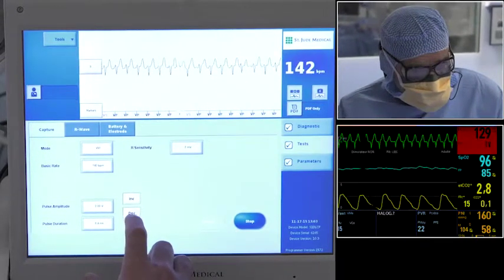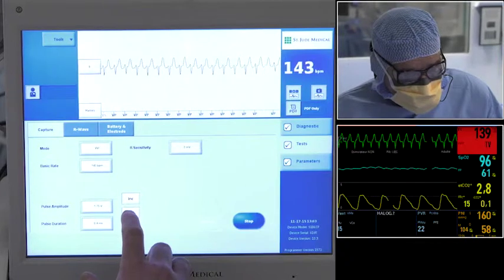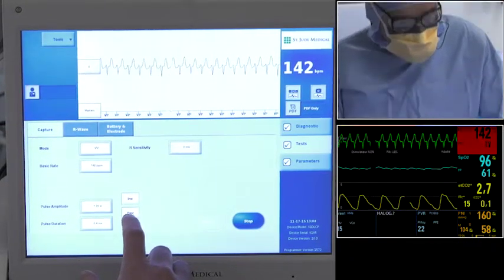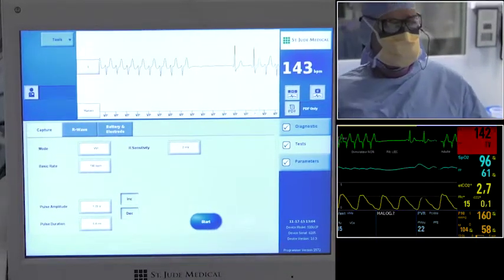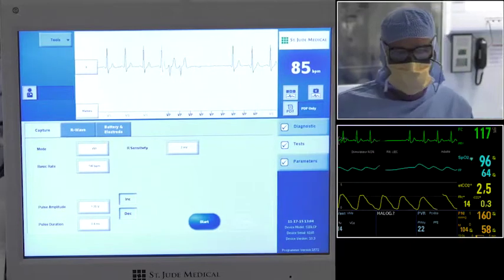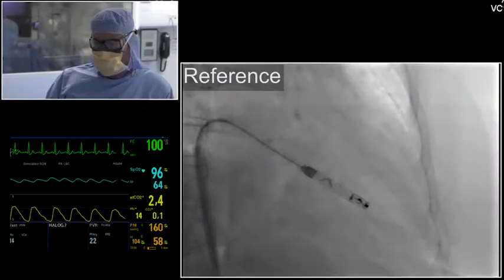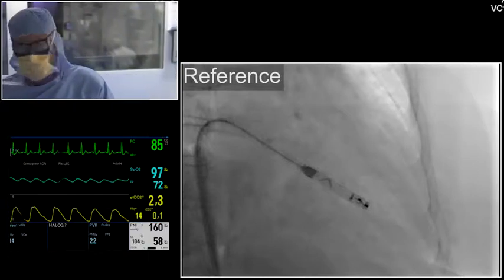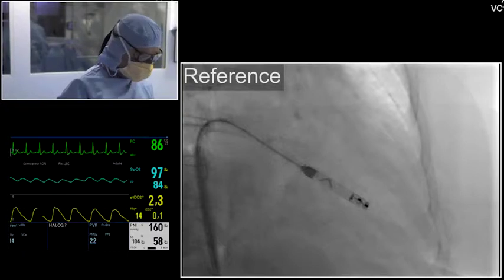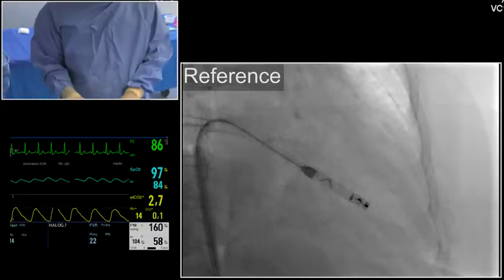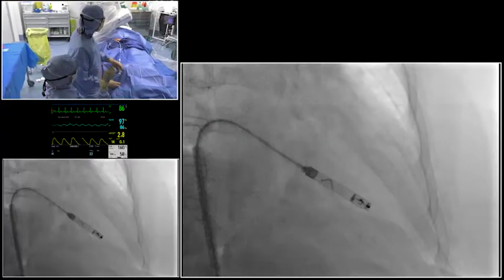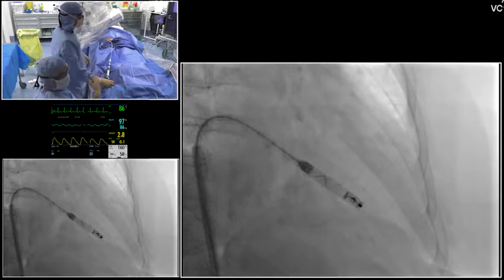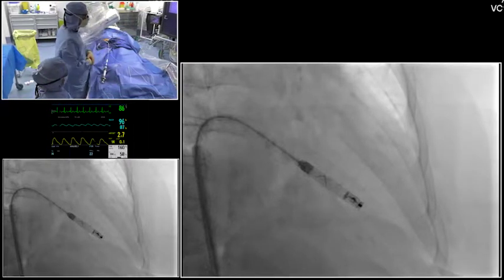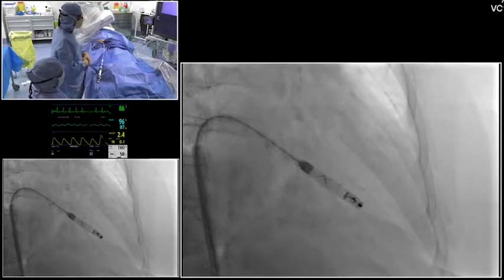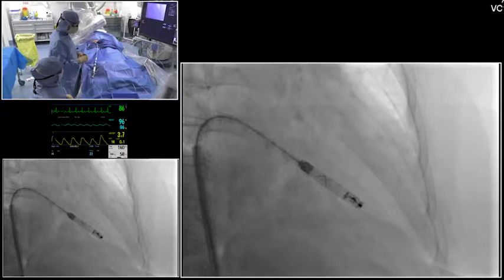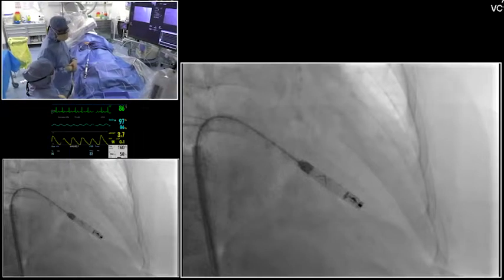2.25, okay. 2, okay. 1.75, 1.5, 1.25. Yes. So the threshold before screwing is around 1.25. So I think we can now screw the leadless, because we are quite sure that the position is a very good position. We have taken the picture as a reference to have the mark to do the rotation. Yes, you can see the marker on the right screen. It's a reference screen, and we will do one turn between 1 and 1.25.